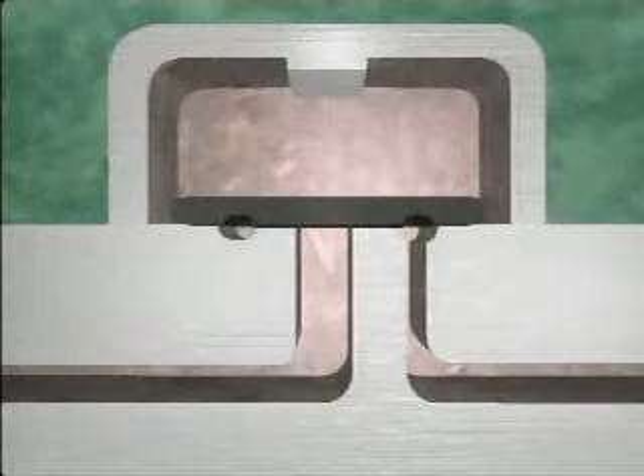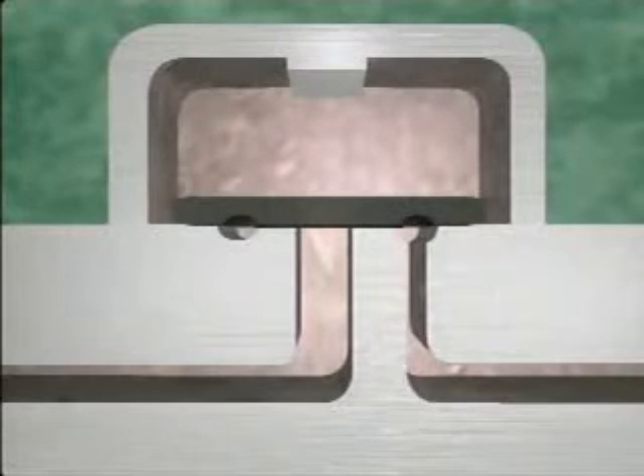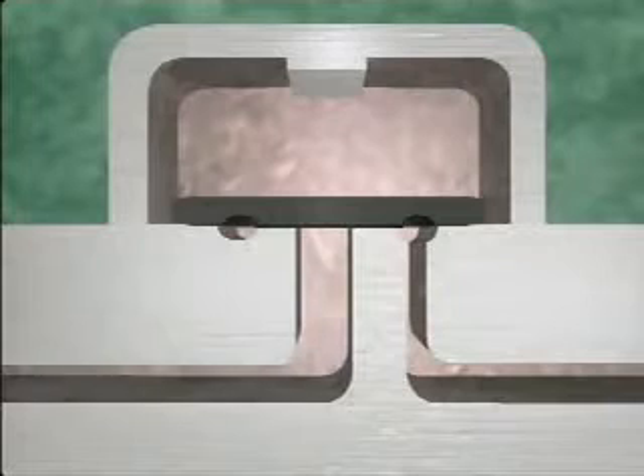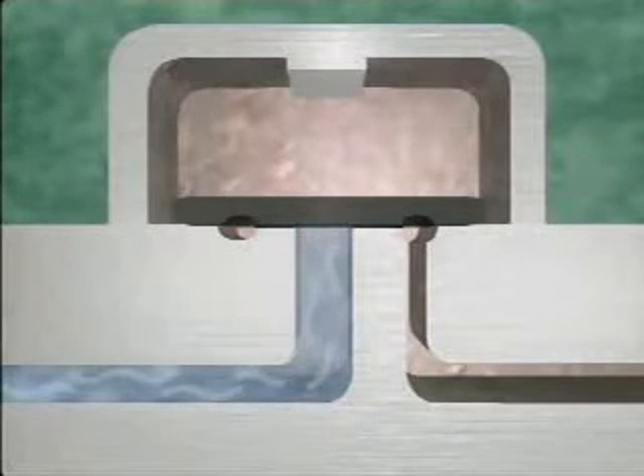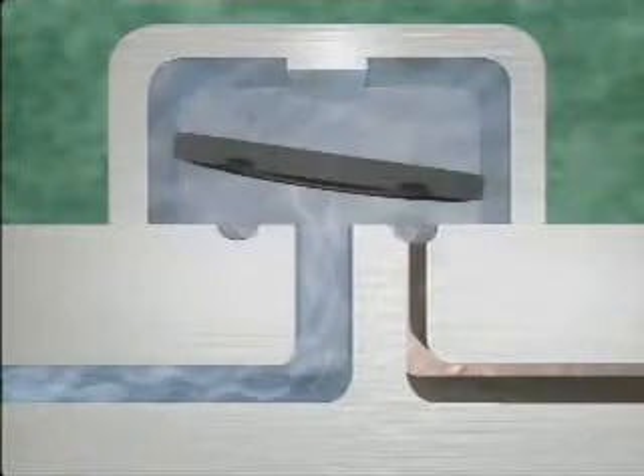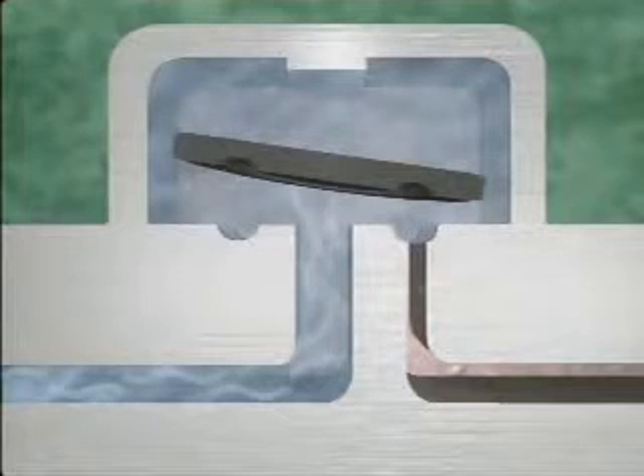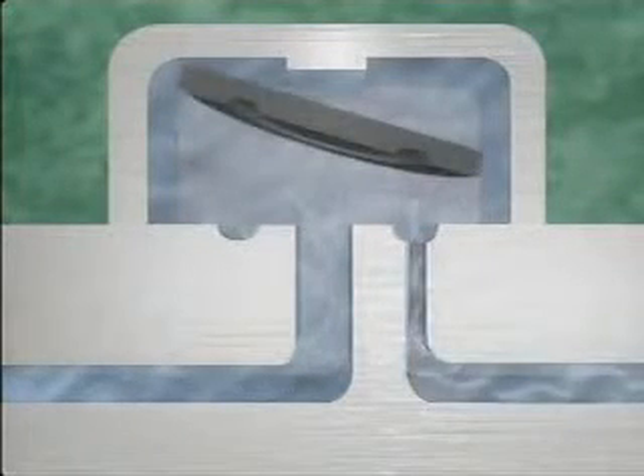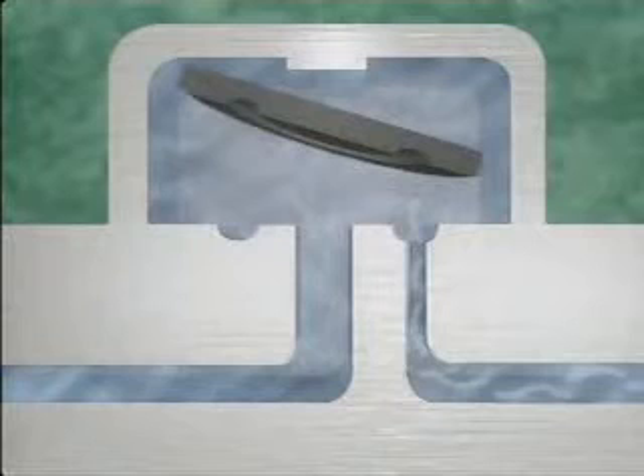At startup, the disc rests on seating surfaces that contact the trap's inlet and outlet. With the disc in this position, the trap is closed. When relatively cool condensate enters the trap, the flow lifts the disc up and opens the trap. The condensate then flows through the outlet and is discharged.